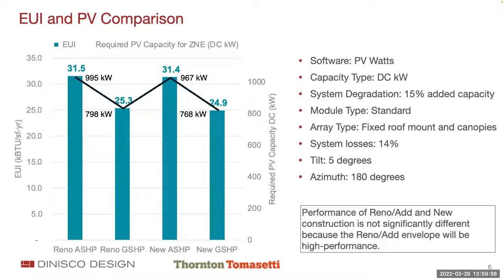So that means that, to my analysis, the assumptions related to coefficient of performance of the ground-sourced heat pump are over twice as high as the air-sourced. Now, my general understanding is that you'll get a coefficient of performance in the low twos for an air-sourced heat pump and the high threes for a ground-sourced heat pump. So that suggests it's about a two-thirds differential, not 120%.